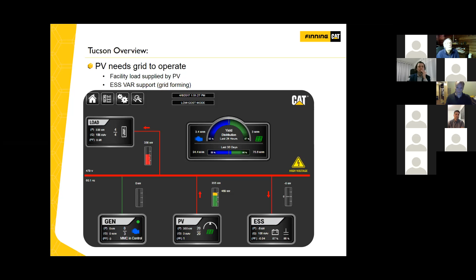This is a somewhat messy slide, but it paints a very good picture of what happens at a remote site. And again, this would be the same as utility, but it shows the importance of the energy storage at site. So the yellow line is your site load, and this is at the Caterpillar Tucson Proving Grounds. So this is a snapshot from a single day, and it shows the green bell curve is your solar power generation going up. And then as that's going up, the diesel power generation, which is your blue, starts to conversely go down, and eventually it will shut off, and that's that solid blue line at the bottom of the screen there.